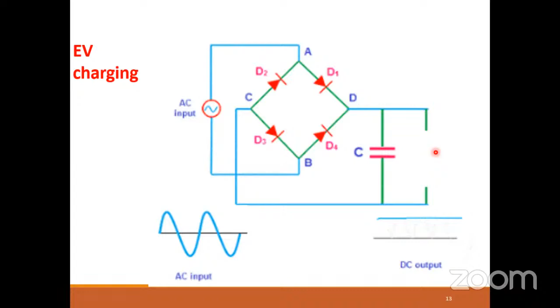The issue is, if you look at the output terminal, you're attaching your battery there, and you get the DC, no issue. But at the same time, on the input terminal, look at the current waveform. This is your current waveform. Now you can realize this pulsating current means heavy harmonics are being introduced into the grid because of this type of network.